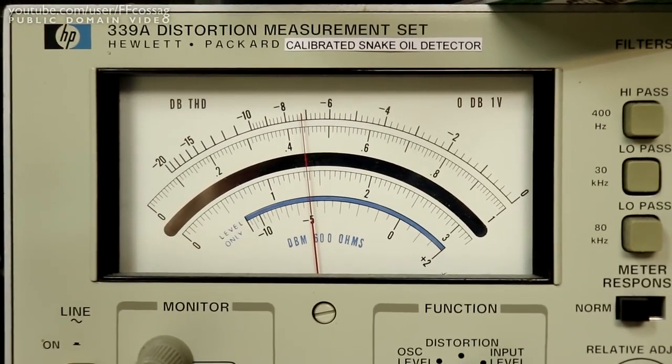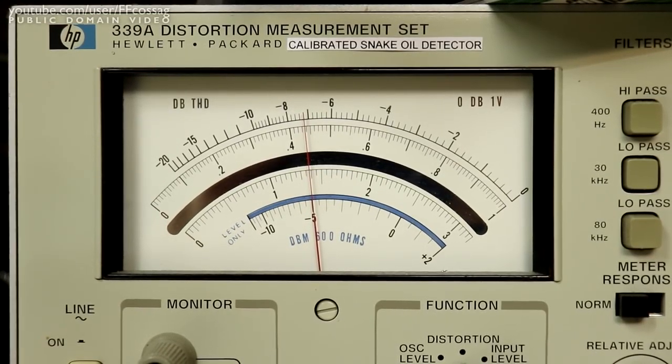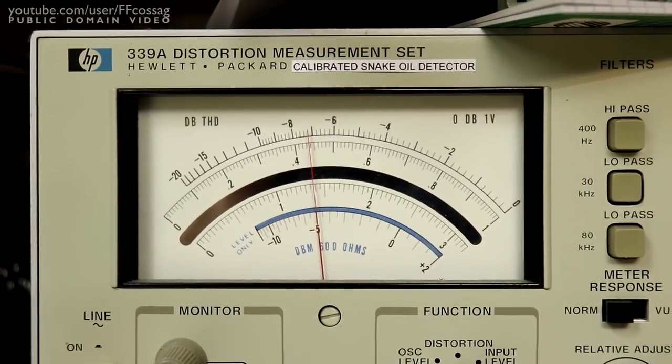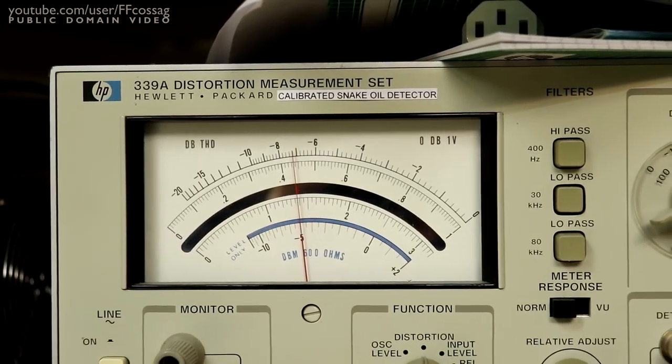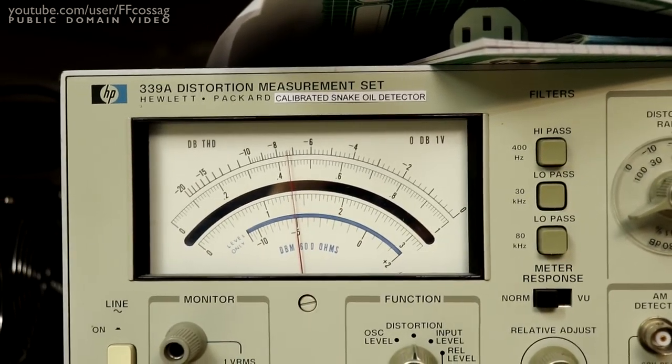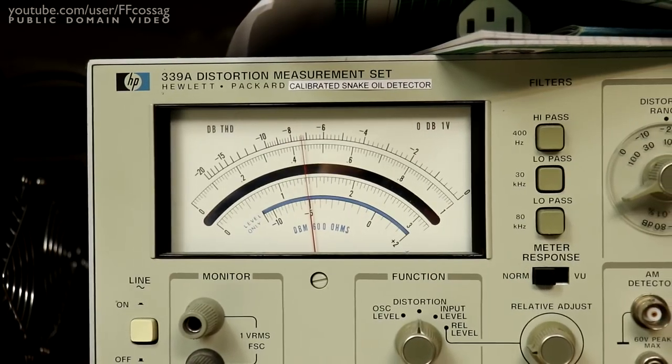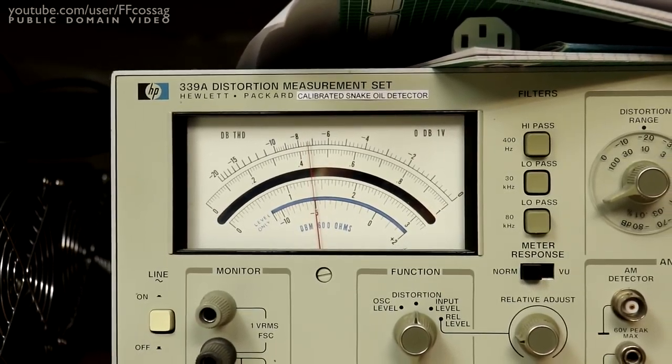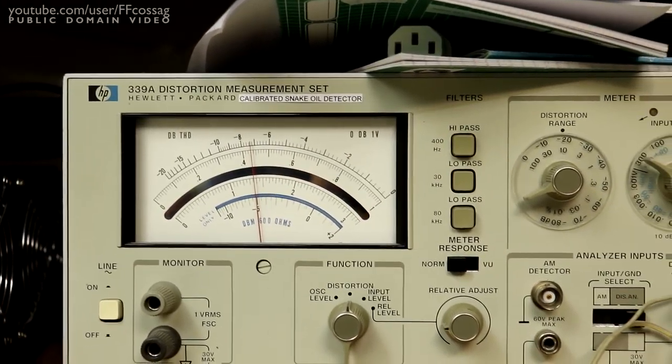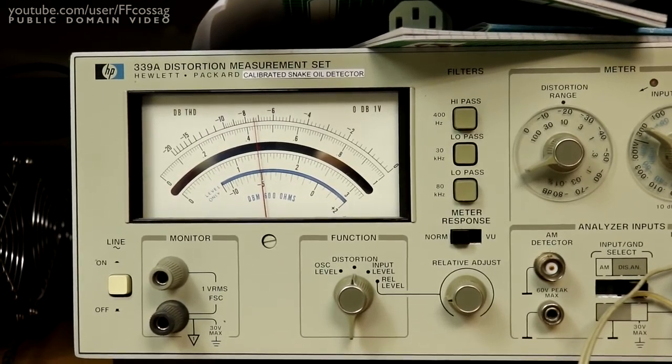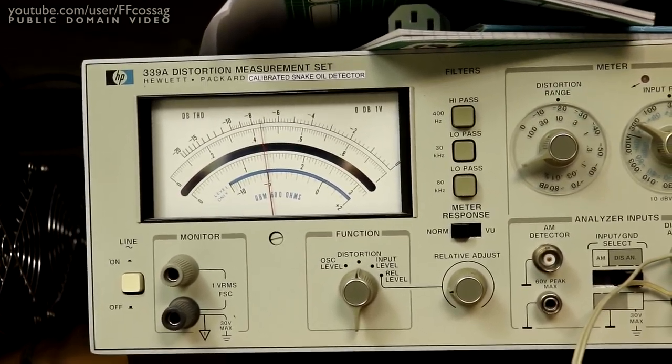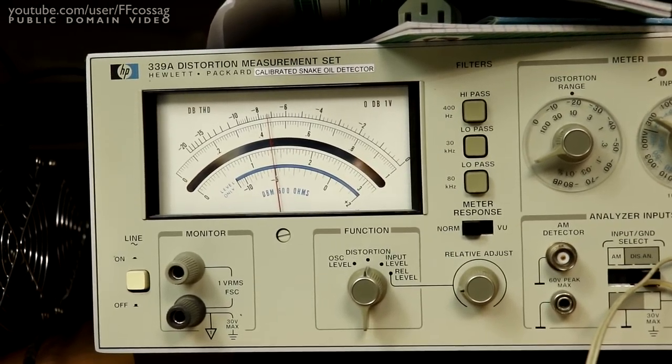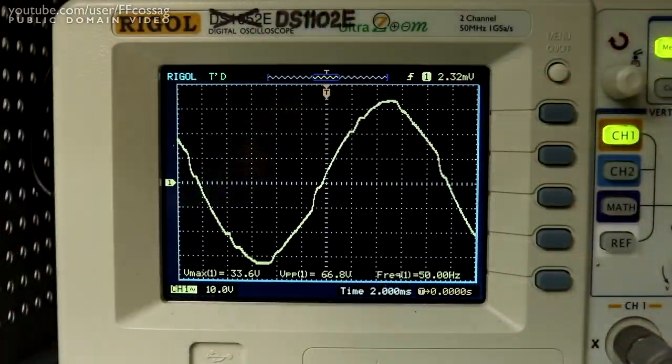I've seen it go to just over 5% on a bad day. Normally distortion of the power grid isn't that big of a deal, but the nature of this particular distortion is causing considerable noise to come out of normal mains transformers and motors. There seems to be quite a bit of horrible looking stuff.